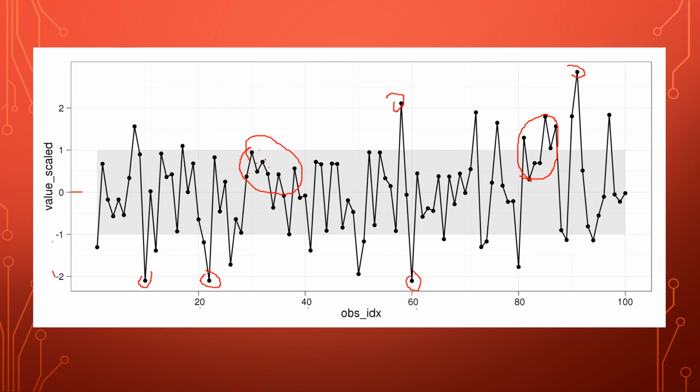When you have something like this, the inspector could come to you and say, I'd like to see the temperature logs for your storage refrigerator and make sure the temperature logs were okay, because this kind of looks like maybe they weren't okay. I'd like to see the QC dates. These are all things that the inspector might note, and these might also help to explain why the QC material did deteriorate.